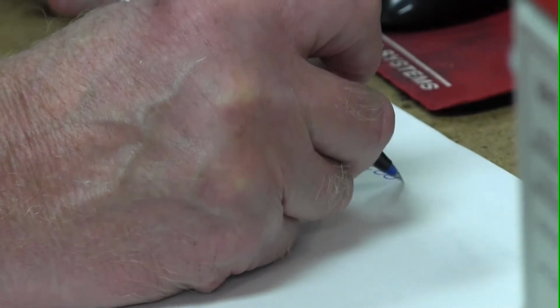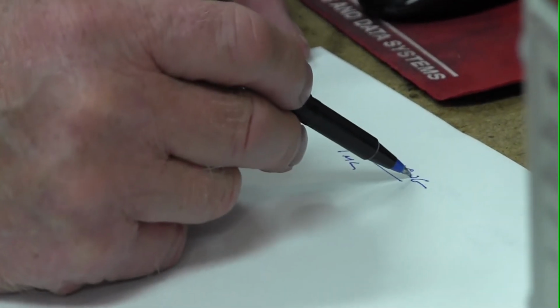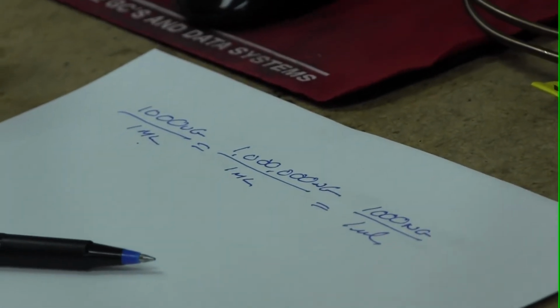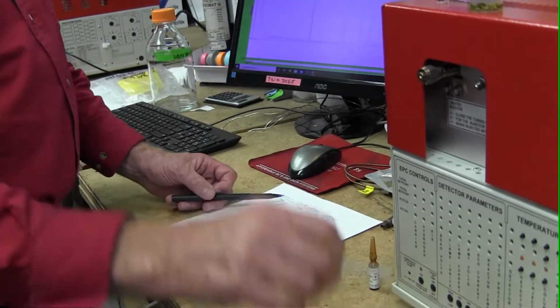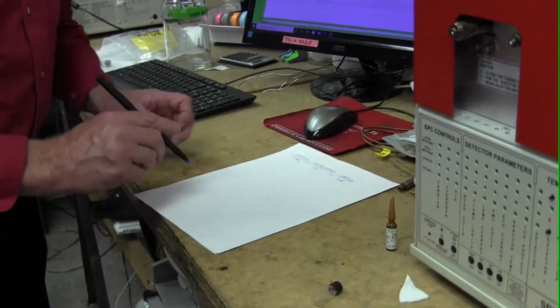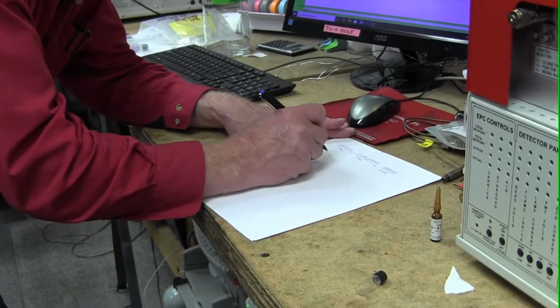So 1,000 micrograms per 1 milliliter is the same as 1 million nanograms per 1 milliliter. And if I divide a million on the top by 1,000 and a milliliter on the bottom by 1,000, it's the same as 1,000 nanograms per 1 microliter. So the reason we want to talk in these units, nanograms per microliter, is that is the weight of the cannabis in the sample that we injected. We're injecting 1 microliter. What we really want to know is how much weight of CBD or THC is in the 1 microliter that I just squirted into the GC. So what we did next in an earlier segment of the video is we had 3 bottles that we made from the Restek.